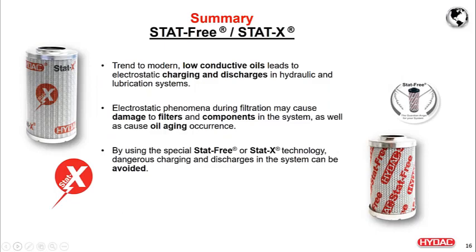So, in the summary, we have the StatX and stat-free element. Stat-free element is normally utilized when the conductivity is between 100 to 500 picosiemens per meter. If the conductivity is lower than that, we normally use the StatX. Even if the conductivity at normal temperature is between 100 to 500, but at a colder temperature where the application is going to be running most of the time, we would use the StatX element.